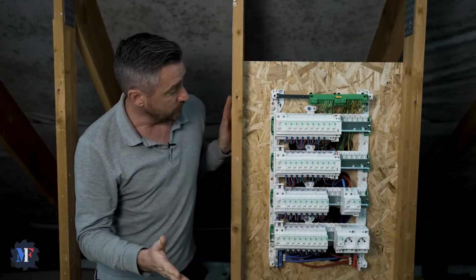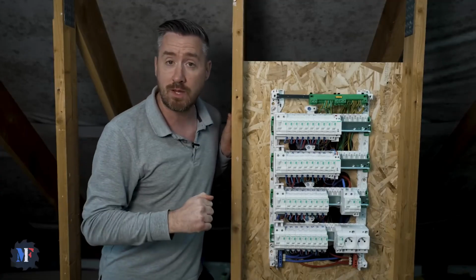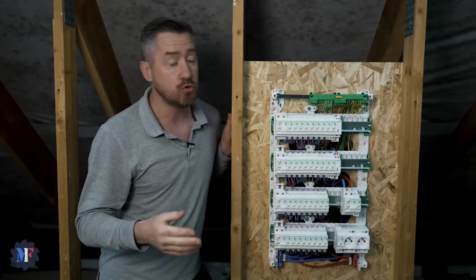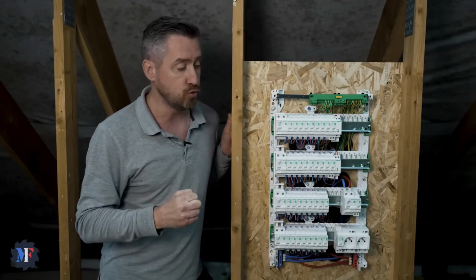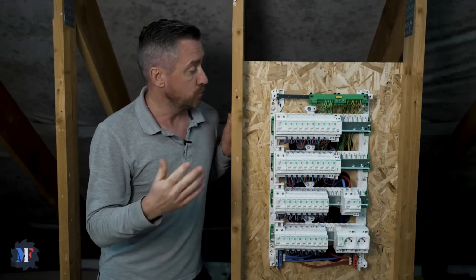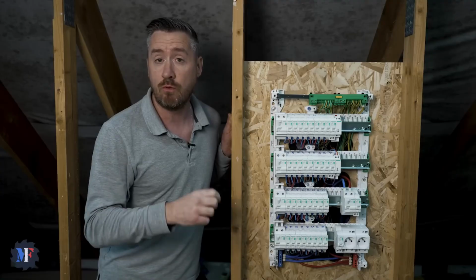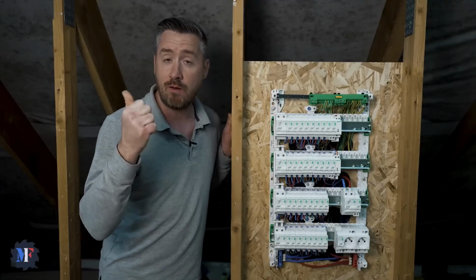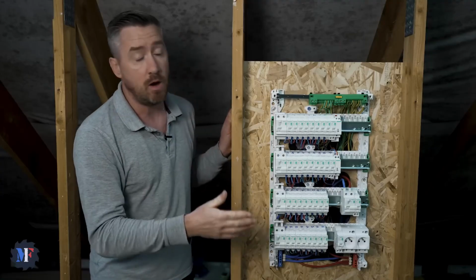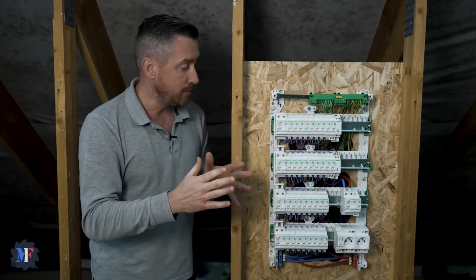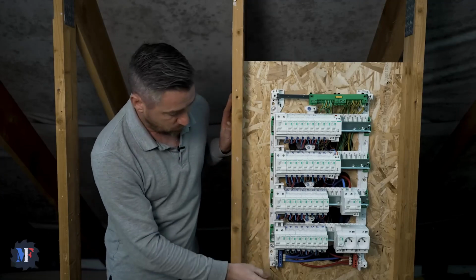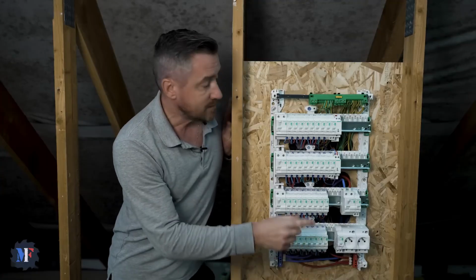Connect, okay, that's done. Now we just need to tap into the lower panel. I'll show you how I was supposed to do it if I kept the lower panel, but I'm going to change it. And to change it quickly, we're going to use 25mm2 terminal blocks for the neutral, the phase, and the ground. And I'll be able to install my GTL, my new panel. Then, of course, we'll tap into the neutral and ground terminals.